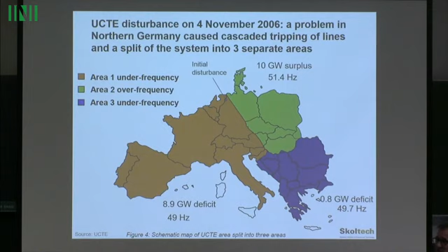There was again a very, very close shave, near failure of the whole system. So here you have a frequency - after separation, this is the east, this is the Balkans, this is the west, with a frequency drop. They were operating at different frequencies, so they tried to reconnect them. You can see those attempts - they were trying to reconnect but were far apart, so it failed here, failed here, and finally they managed to connect them after half an hour or so.